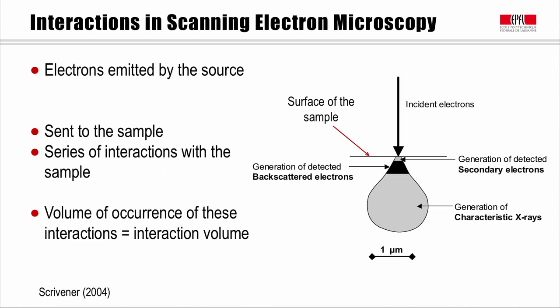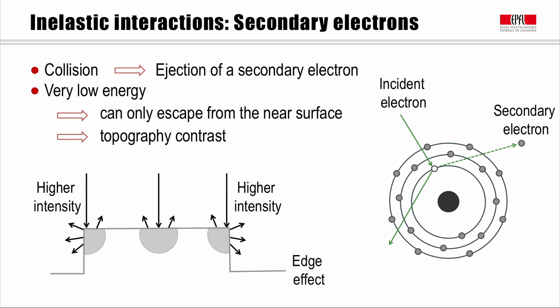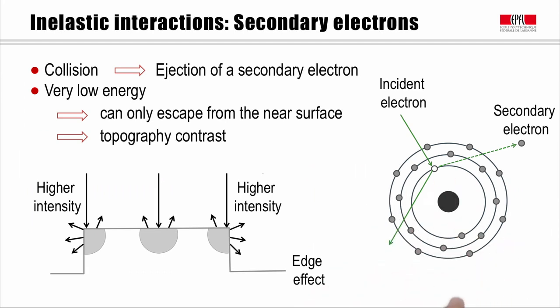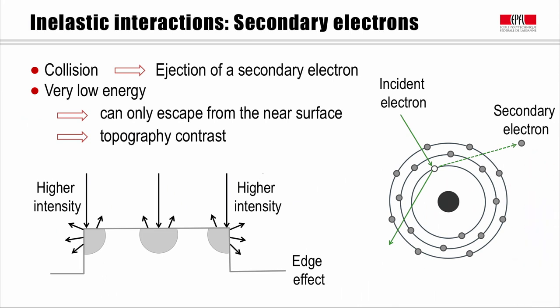These interactions can be either elastic, with no energy loss, or inelastic. The first kind of interaction occurs when an incident electron collides with an electron of an atom of the sample. From this collision, the incident electron is deviated and the bound electron is ejected. This ejected electron is called a secondary electron, or SE. The energy of secondary electrons is typically lower than 50 eV, which is very small. Thus, if these electrons are to be collected by the detector, they have to be formed very close to the sample surface. If they are formed deeper in the sample, they would face interactions before reaching the surface and would be absorbed due to their low energy, and would not be collected by the secondary electron detector.